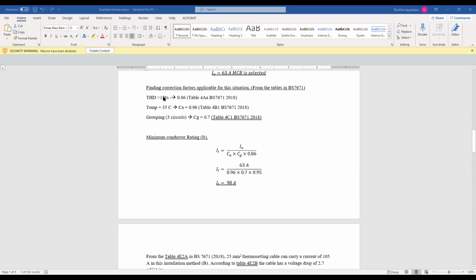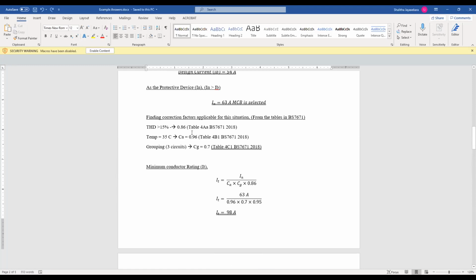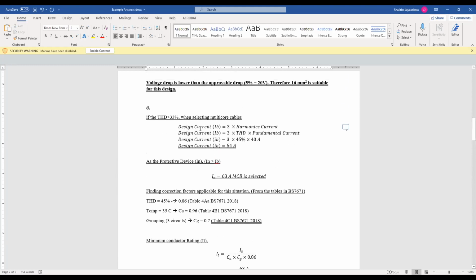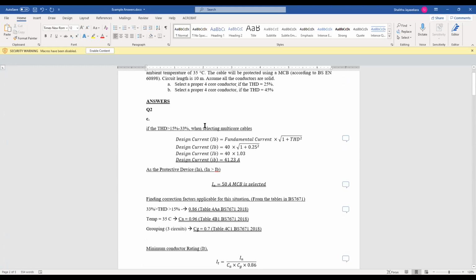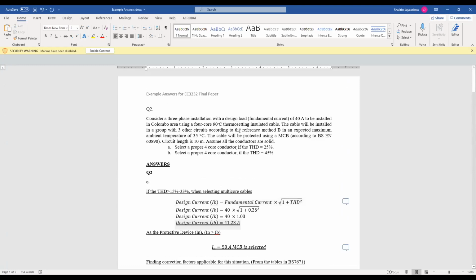So in here, you should do a small correction. This should be equal to 45%. So if it is higher than 45% also, we are not going to add this 0.86 value. So in here it is 45%. So therefore we have to consider this 0.86 rating factor. So that's it about the design.